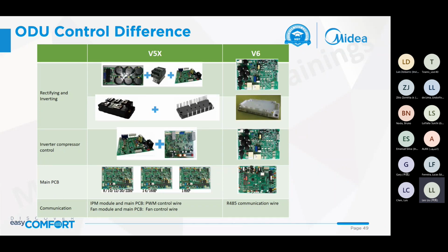And the next one is communication. For the previous generation, the IPM module used a PWM control wire to the main PCB. It's a very special cable. And the fan module between the main PCB, the fan control wire, is also a special cable. But for the current generation V6, we use the universal RS485 communication wire. This wire is quite common. So we can see a lot of improvement for the components.